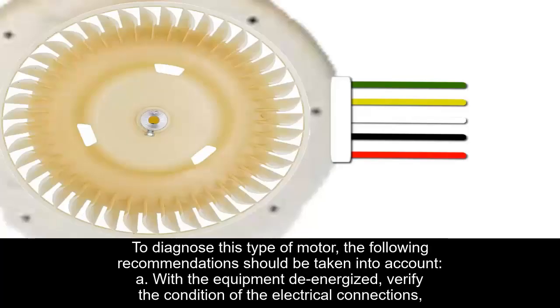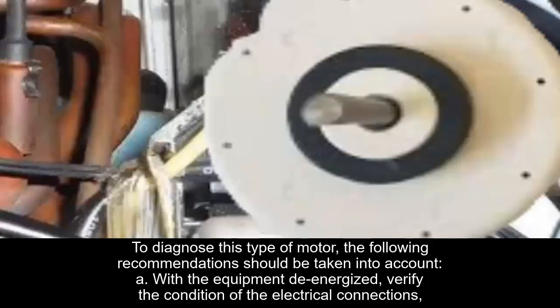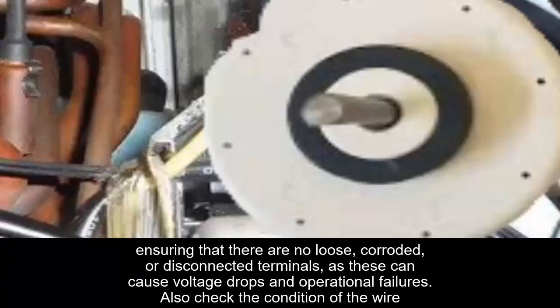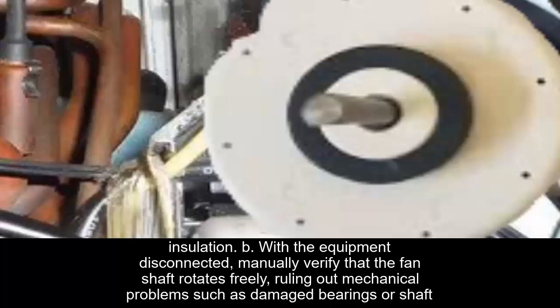To diagnose this type of motor, the following recommendations should be taken into account. A. With the equipment de-energized, verify the condition of the electrical connections, ensuring that no loose, corroded, or disconnected terminals are present, as these can cause voltage drops and operational failures. Also, check the condition of the wire insulation.